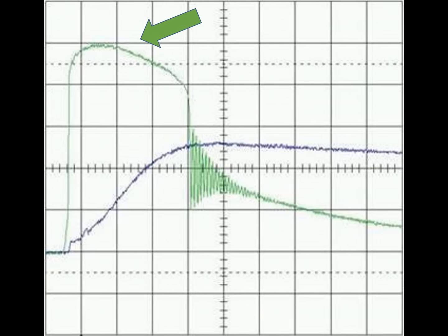The green waveform is the let-through for a shunt protector. This shows that the shunt protector limits the peak voltage seen by the equipment but does nothing to attenuate the very high rate of voltage rise seen at the start.